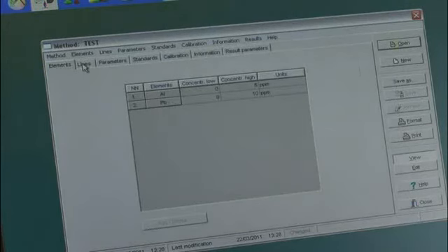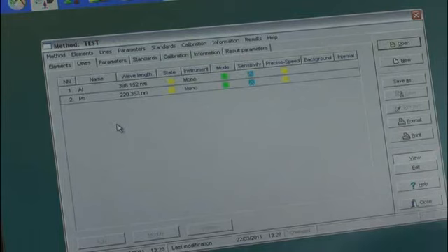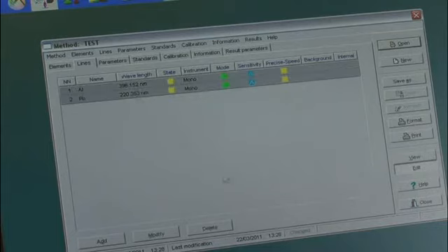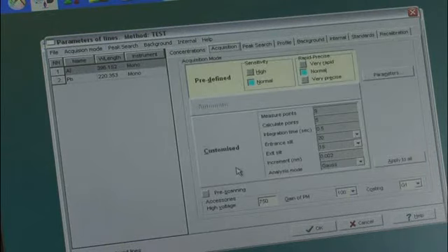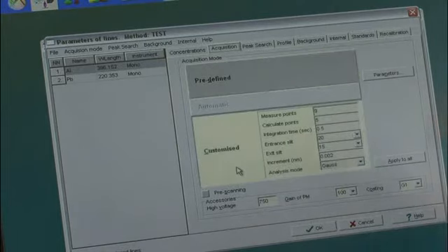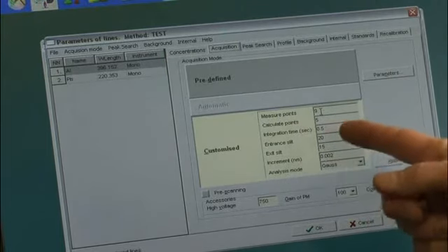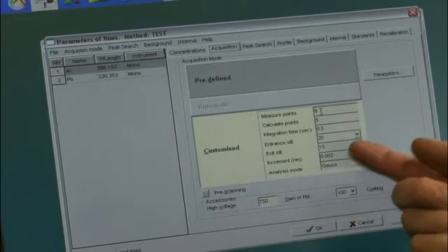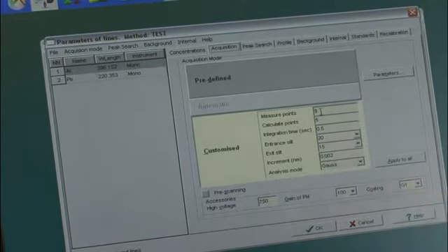Then I want to tell it how I want to analyze those lines. So I'm going to go to lines, have to be in edit, highlight both of those, modify, acquisition. So there's a couple different ways to do your acquisition. What I usually do is Gaussian, curve, asymmetrical slits, entrance is large, exit is small. My integration, it's going to do 9 measurement points, and it's going to calculate the concentration on 5 of those 9. The acquisition time will be half a second per point. My increment will be 2 picometers per point, and I'm going to use Gaussian.